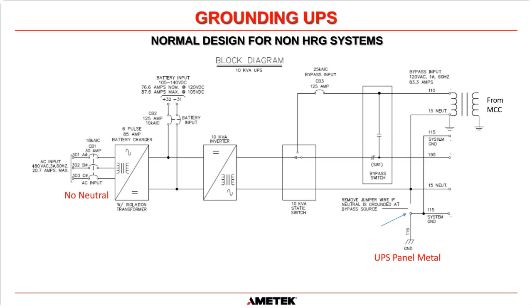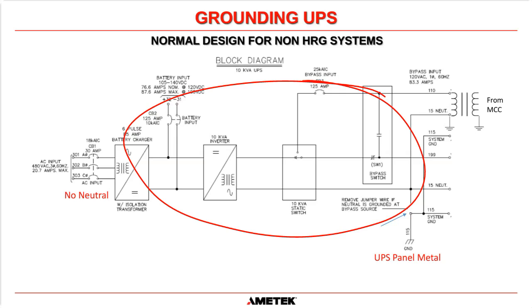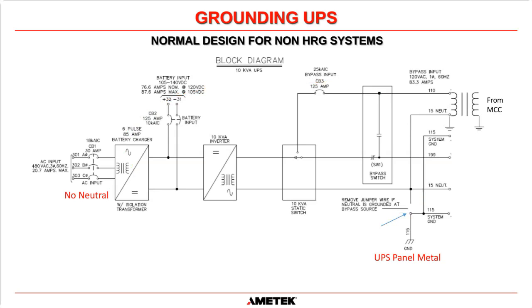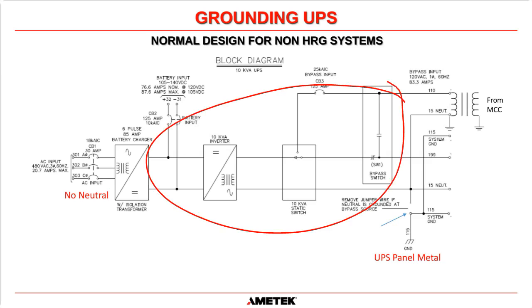And there's a good reason for that. It's because a transformer tends not to fail, especially dry type transformers. So the expectation is that this transformer is going to be installed and then it's going to run for years and years and years, 20, 30, 40 years without any issues, if it's a dry type transformer and it's not pushed to the limits or too much current has been pushed through it. A UPS, on the other hand, whether it's a commercial UPS that usually has 8 to 10 years life, or if it's one of our AMETEK SCI industrial UPSs, it has a lifespan of 20 years. So the expectation is this UPS may need to be replaced after 20 years before this transformer will be replaced.